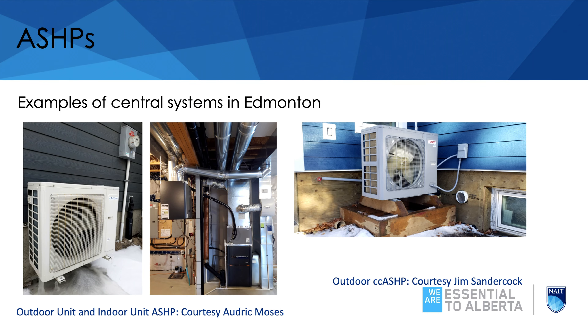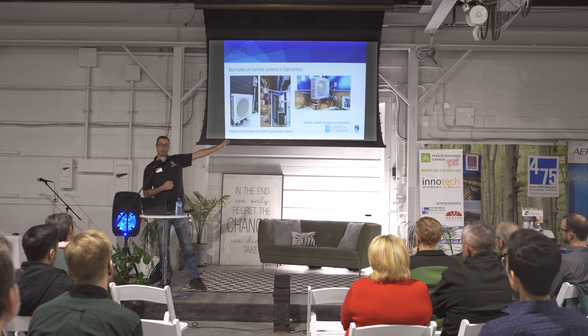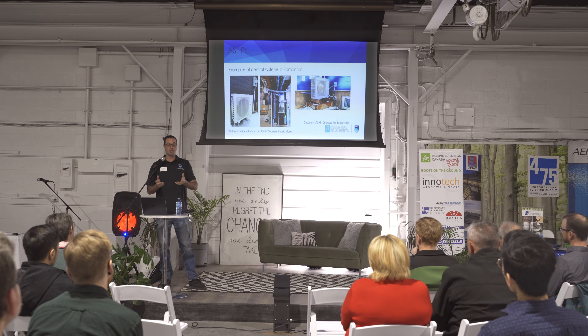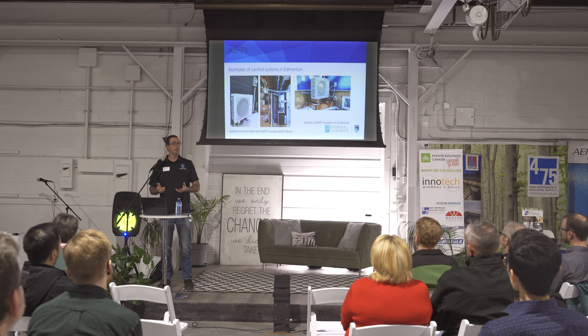Do they work in Edmonton? They do. There are plenty of houses in Edmonton with heat pumps — most of them are high-performance houses that require smaller loads. One example is a Tosot heat pump, and another is my friend's house built about 15 or 16 years ago. That one is not a cold-climate heat pump and he runs it all winter long, even at minus 20. The efficiencies are not great on it, but it still heats the house fine. He has electric backup, an air handler with an electric furnace backup, and an HRV.